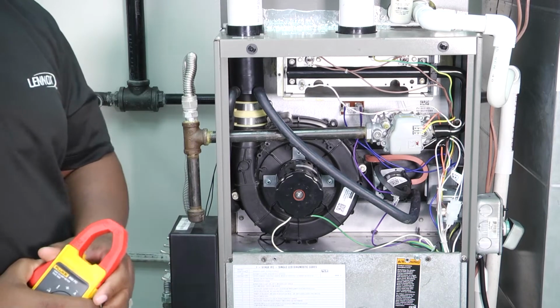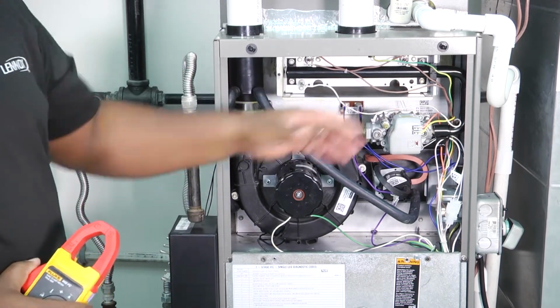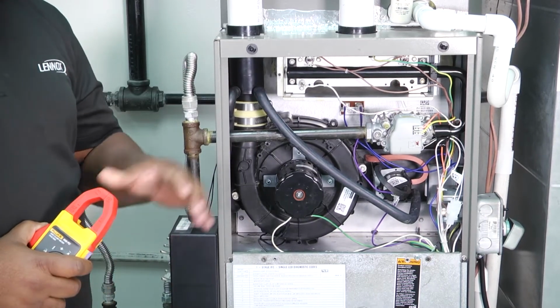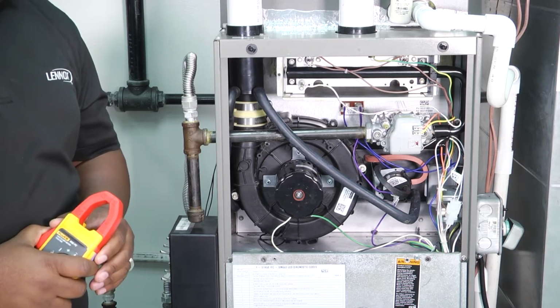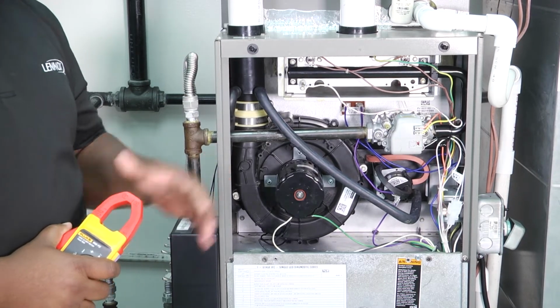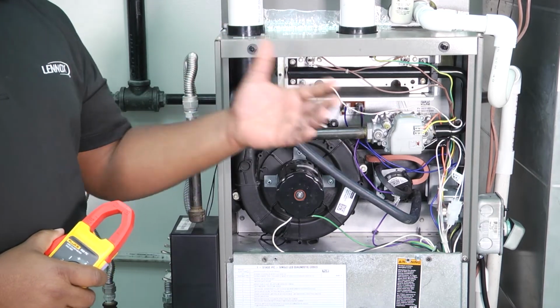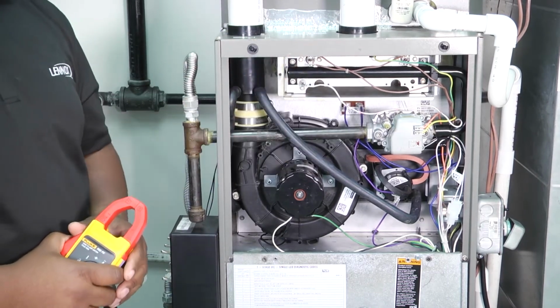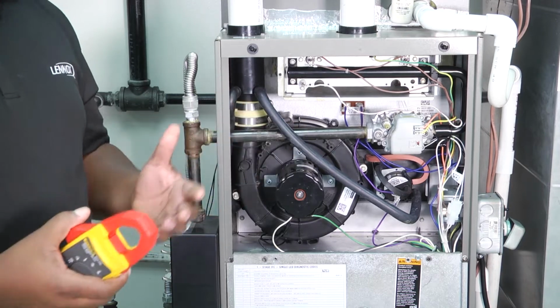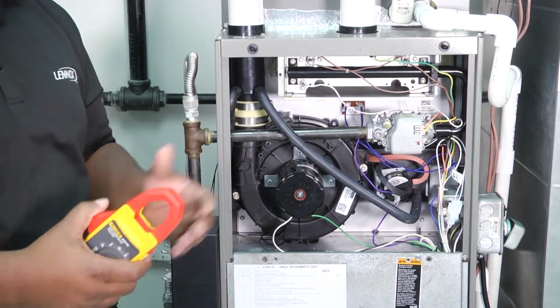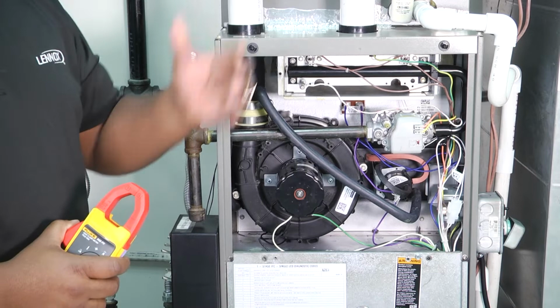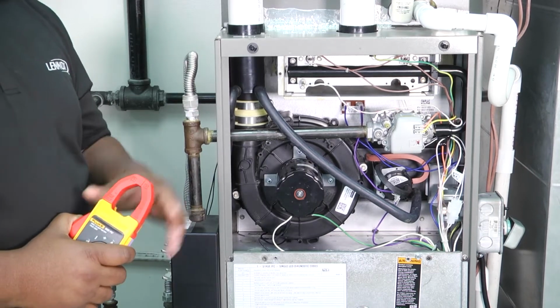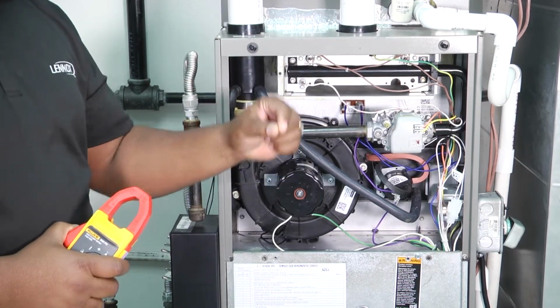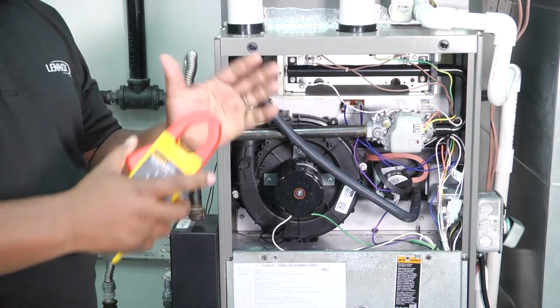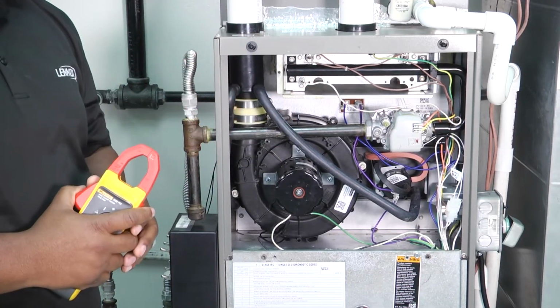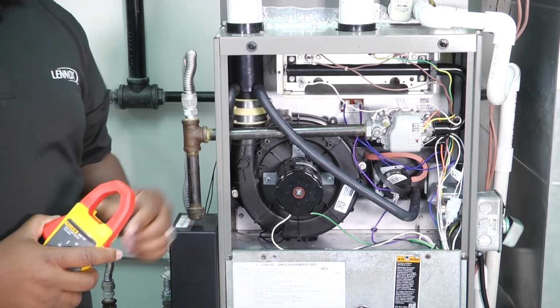So we want to make sure our motor is operating within manufacturer specs. There's a couple of other components that we need to check as well. One of them is a hot surface igniter. Depending on which type of hot surface igniter you have, there's going to be a list of tolerances or resistance that each one can have. Some of them are as low as 11, 12, 13 ohms of resistance. Some of them are as high as 150 ohms of resistance. You have to know the type, and then you also have to know, based on that type, what the manufacturer says is the tolerable range of resistance for that particular igniter.